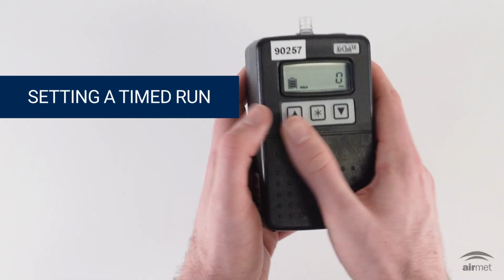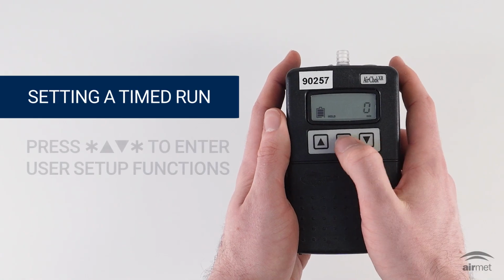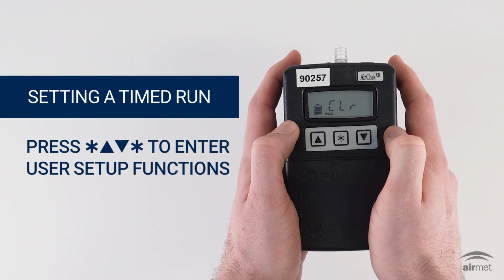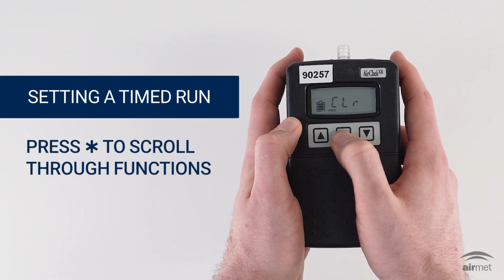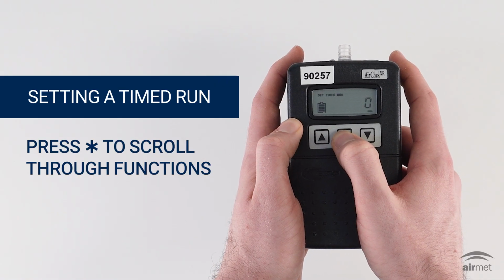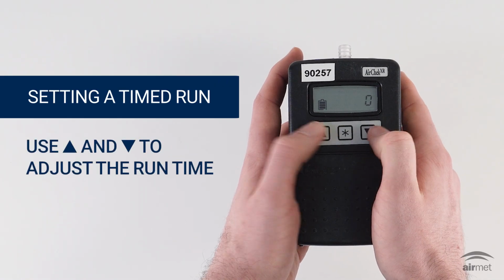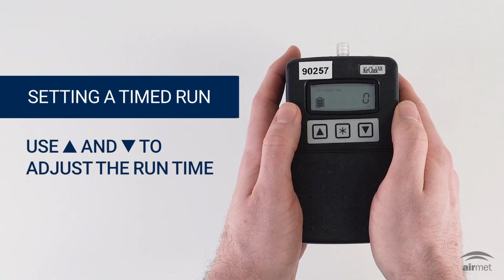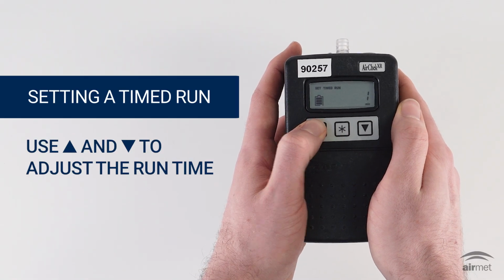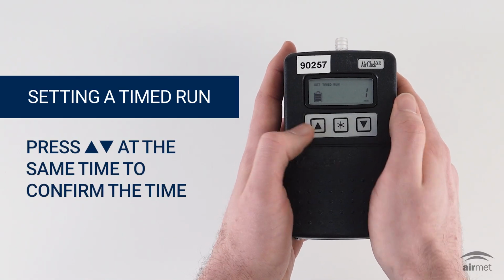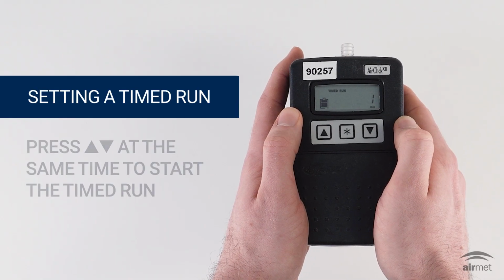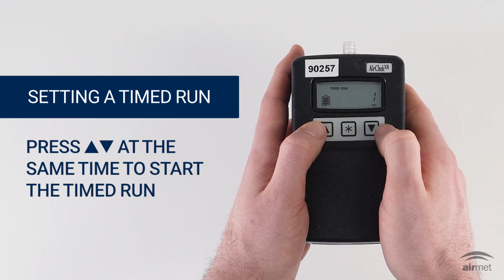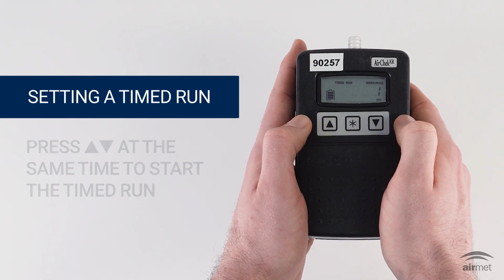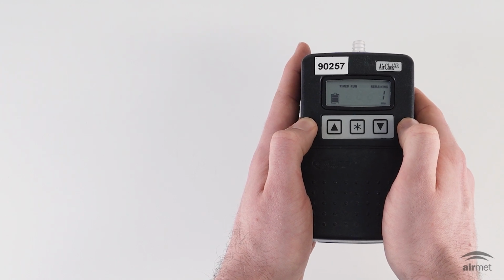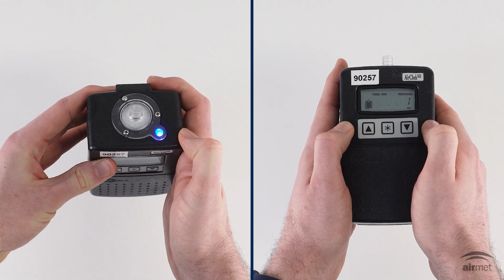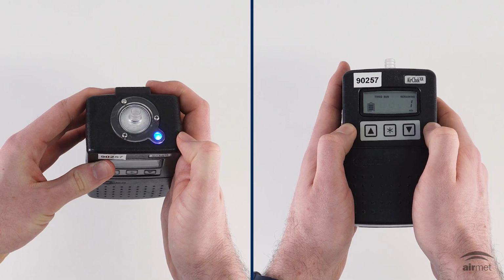Setting a timed run. With the pump in a non-running state, press star, up, down, star to enter the user setup. Scroll using the star key until you see set timed run. Use the up or down arrows to change the number of minutes from 1 to 9,999. Press the up and down arrow keys together to accept and exit. Then start the timed run by pressing the up and down arrow keys together. The pump will now run until the time elapses and then will automatically stop. During the run, the blue LED will flash and the display will show the time remaining.